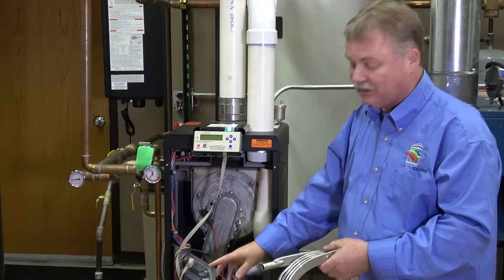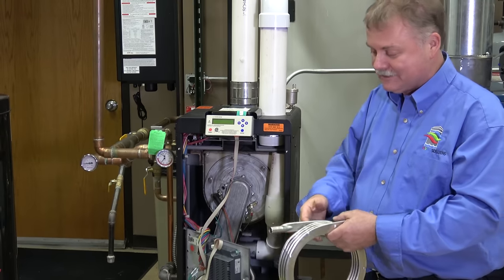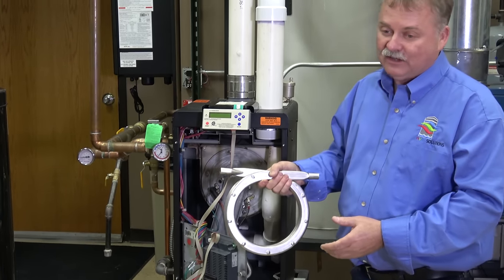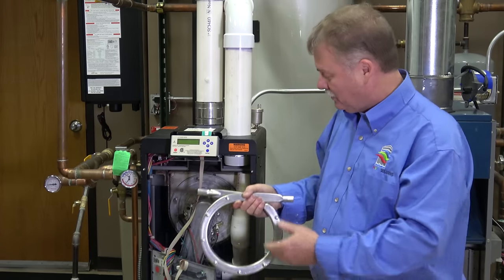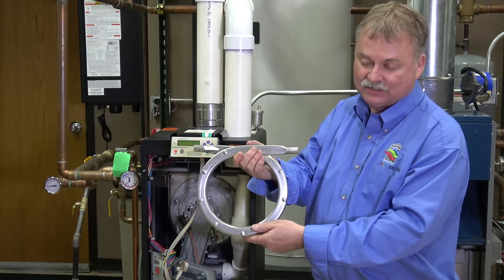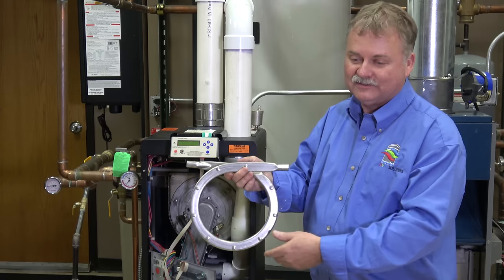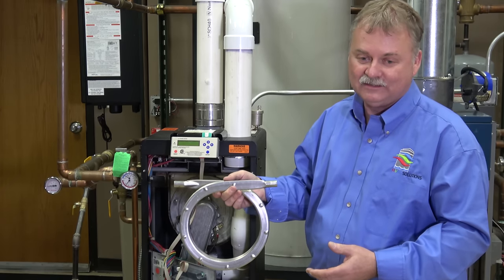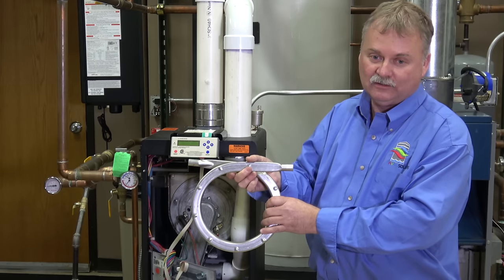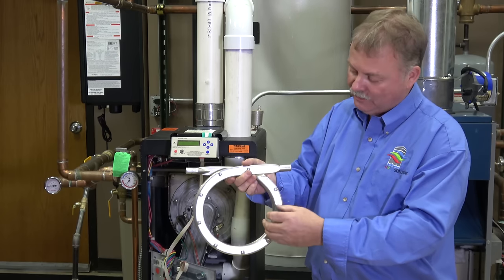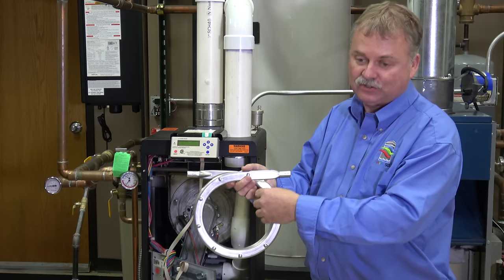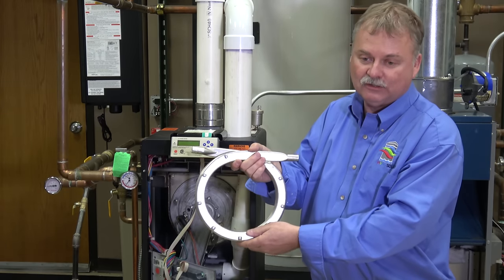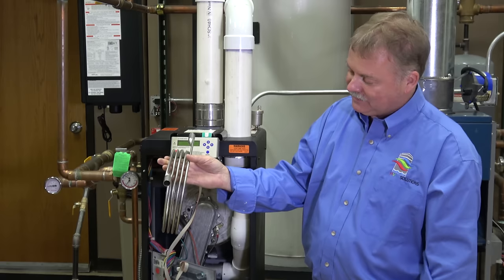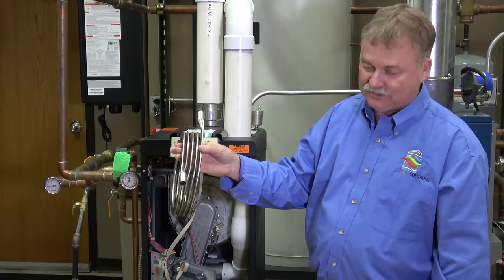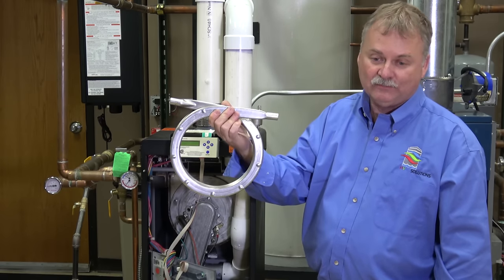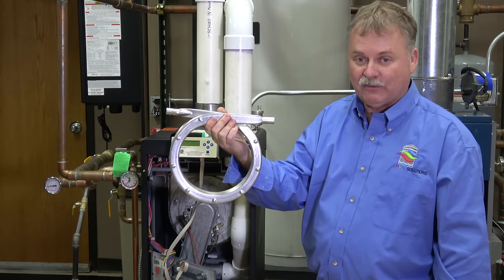That's why a lot of this market is going to the high efficiency boiler. There are different styles of high efficiency boilers. This one here, let's talk about, this is the heat exchanger. This is considered low mass. What we mean by that is really not the weight, it's more how much water is in here. How much water am I using to transfer those BTUs? This is considered low mass. As you can see, this is about 10 feet of stainless steel tubing. This might hold 2 cups of water. Not a lot of water.